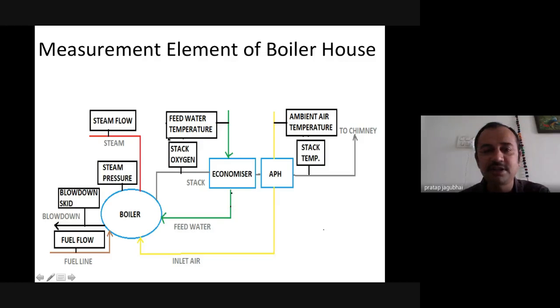Let me give the block diagram of the boiler house. The boiler house consists of the boiler, which is a combination of furnace, drum, and all the burners and combustors, in the case of an oil and gas fired boiler. Then it has heat recovery equipment, if available. This heat recovery equipment is in the form of an economizer, where the flue gas heat is utilized to raise the water temperature closer to the steam temperature, so that the boiler can easily generate steam with very little fuel consumption. Then you can make the ambient air hotter before taking it inside the furnace with the help of an air preheater.